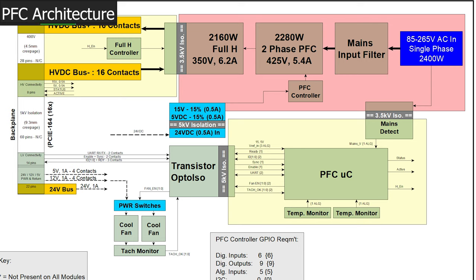The intermediate bus voltages are defined here as well. The PFC should generate a maximum of 425 volts, which is stepped down by the full H converter to the nominal DC link voltage of 350 volts. Note, we established 5kV of isolation between the low voltage circuitry and everything else, where the low voltage circuit is referenced to protective earth. The 3.5kV isolation between mains and the DC link is what allows the DC link to be optionally tied to neutral on either output without consequence.